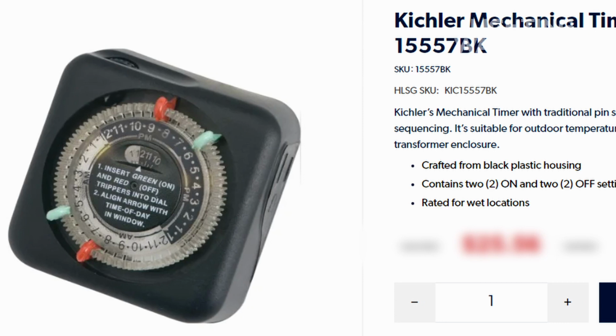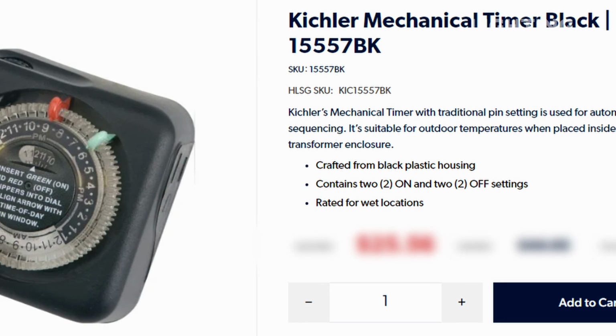If your best location is going to eliminate the option of a photocell, you can go with a standard timer like this, which operates according to the time of day you set. You could have your lights come on at something like 5 p.m. and go off at 11. This would be a simple way to give you a predictable schedule. There are also these great things called astronomical timers, which know when the sun sets and rises in your area, and can be programmed to turn on and off based on those events, including settings like turning off so many hours after sunset, or turning back on an hour before sunrise.